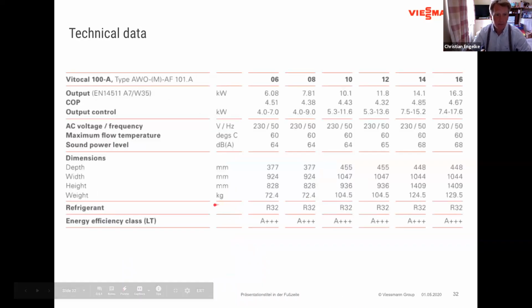Some technical data you will see from our brochures. So we have the models from 6 kilowatt to 16 kilowatt. The output, as I said, from 6 to 16. The COP value at 7 degrees outside temperature and 35 degrees flow temperature is from 4.5 to about 4.7, so a very, very efficient machine. Single phase machine, maximum flow temperature of 60 degrees, and then sound power level from 64 dBA onwards up to 68.